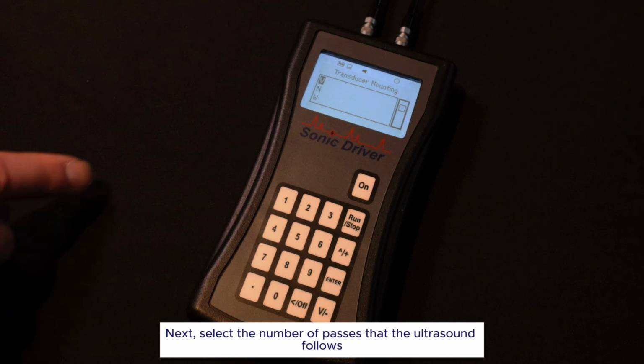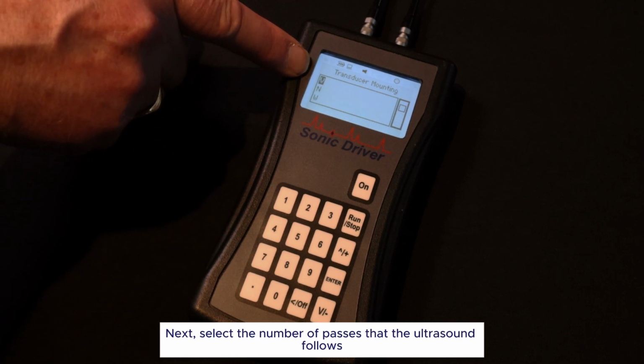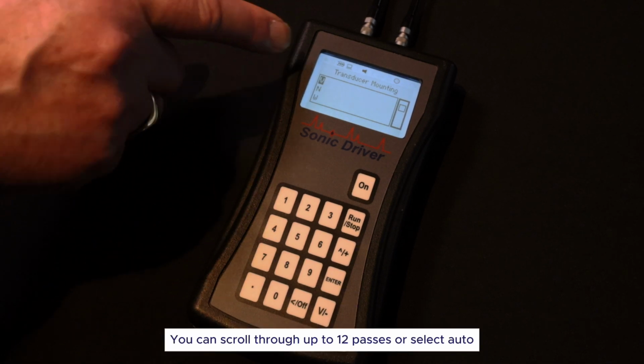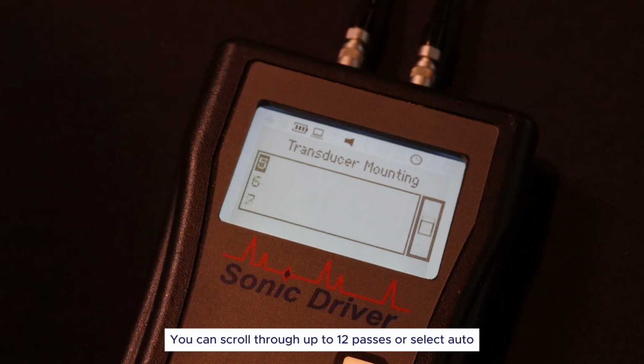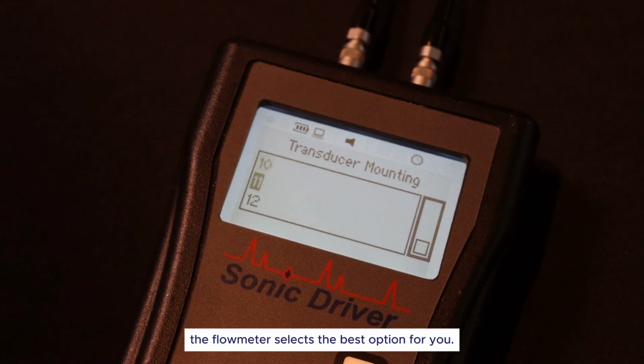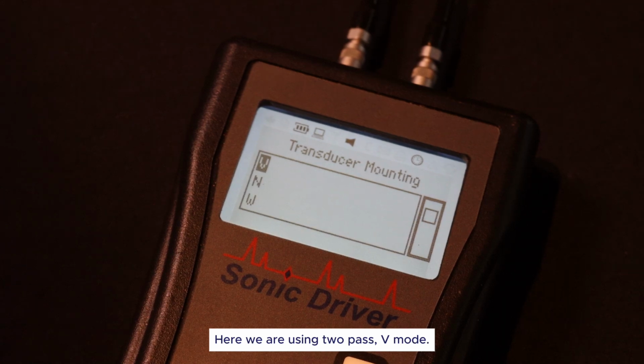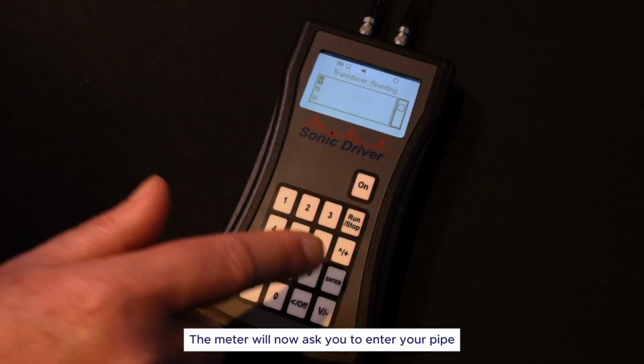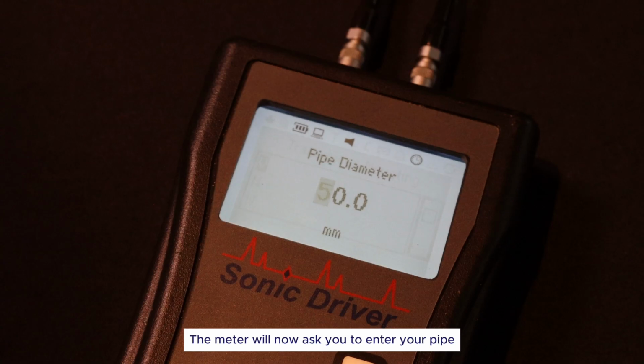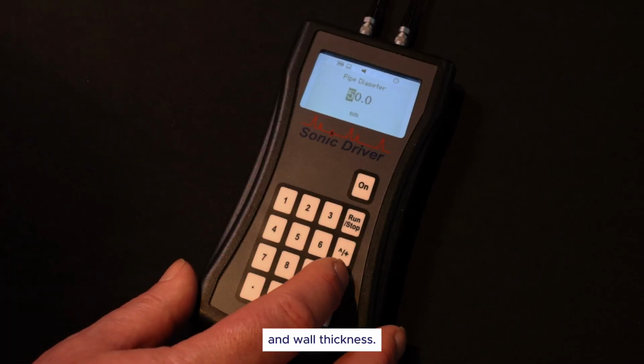Next, select the number of passes that the ultrasound follows across the pipe. You can scroll through up to 12 passes or select auto, in which case the flow meter selects the best option for you. Here we are using 2-pass V mode. The meter will now ask you to enter your pipe outside diameter and wall thickness.